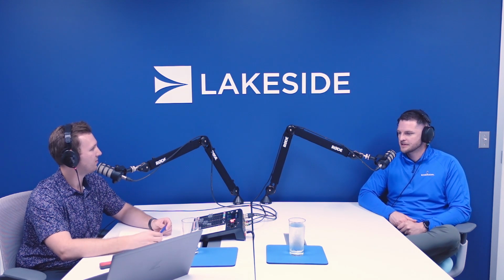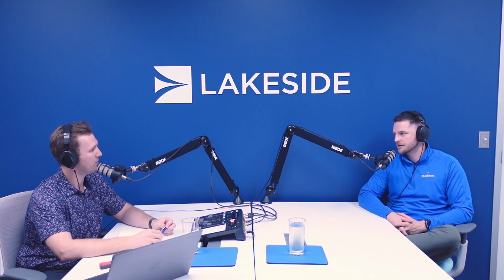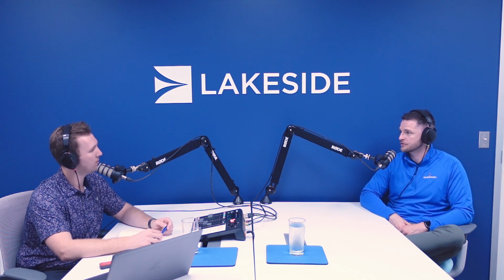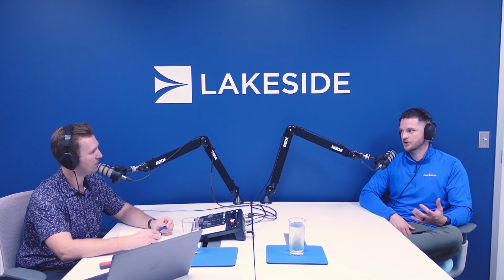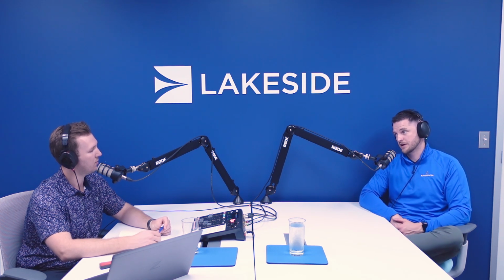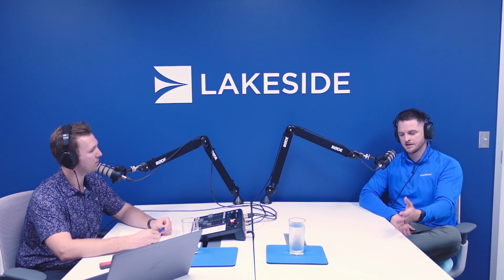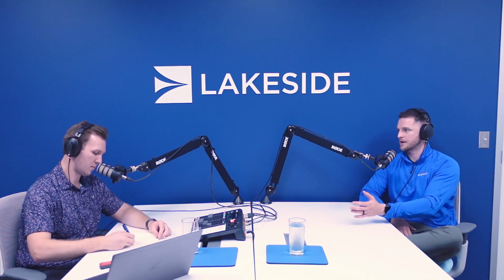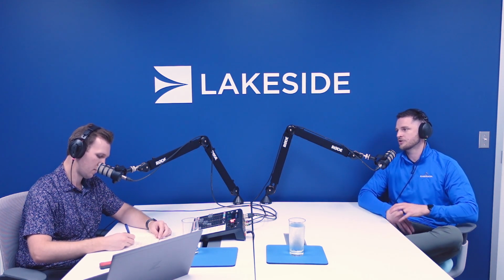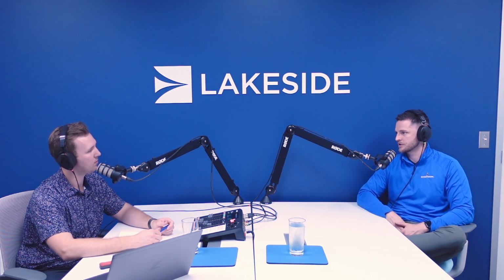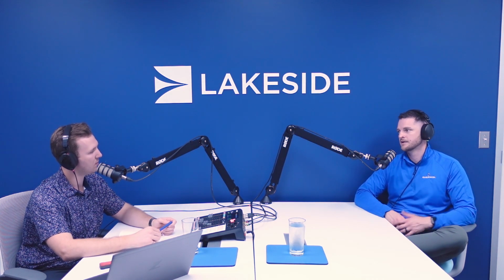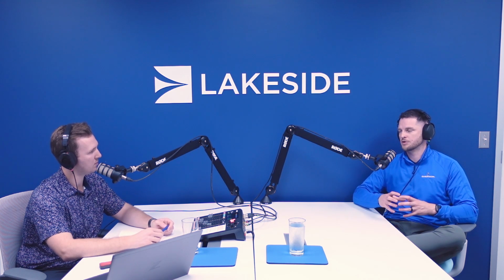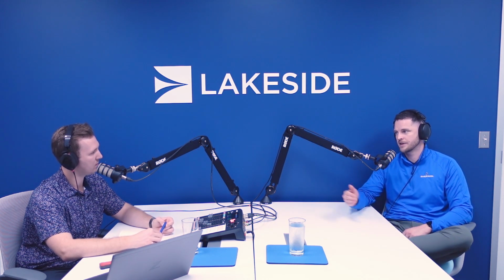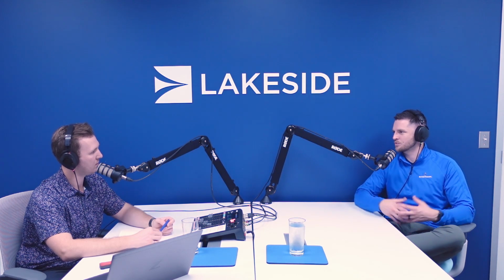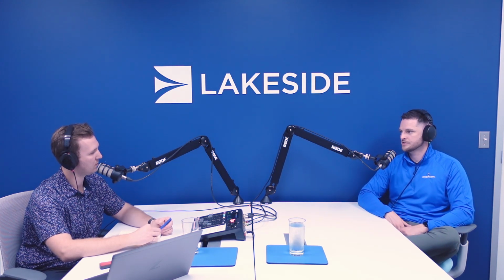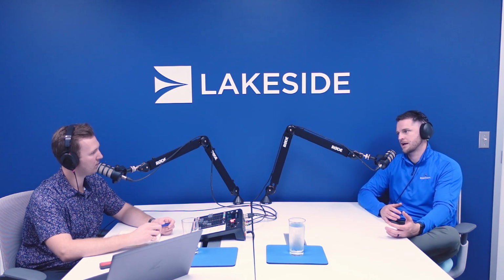And like you said, we have things where we can calibrate a unit to a site. If you're looking at our PIOX units, our mass flow unit, and you wanted to output a very accurate concentration measurement, we can calibrate that unit out in the field. So we can do a timestamp basis, say, hey, the sound speed that we see here, here's your weight percentage. We add that. We basically teach that meter a new version of the accuracy. We can do the same thing with our hydrocarbon, so API, when you're putting it on a pipe. We can help the meter drill down on that single point cal of whatever that media is. Those are things we can do to help raise the repeatability, so out-of-the-box accuracy as opposed to after-calibration accuracy.